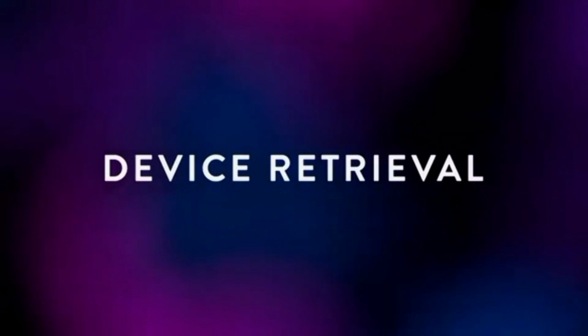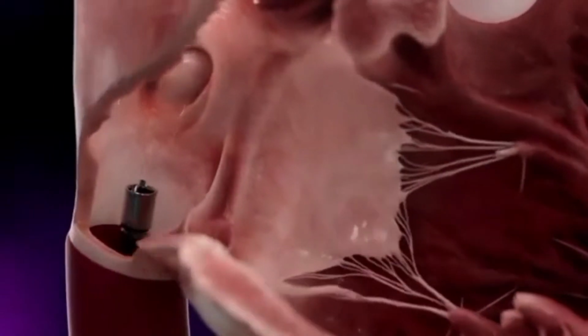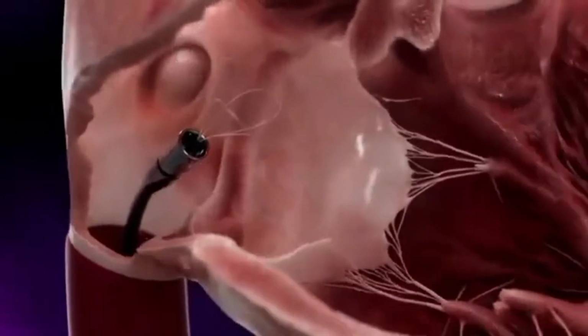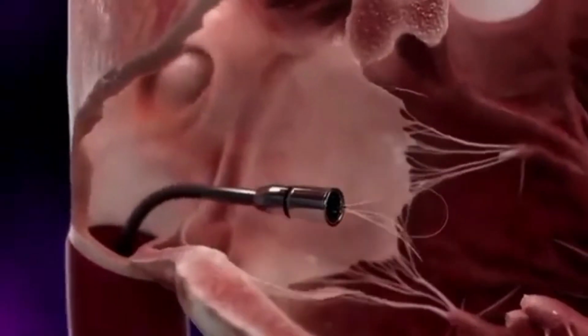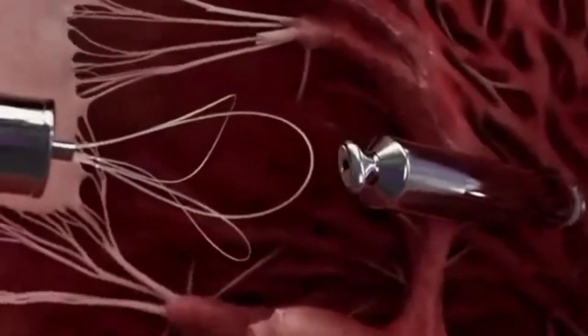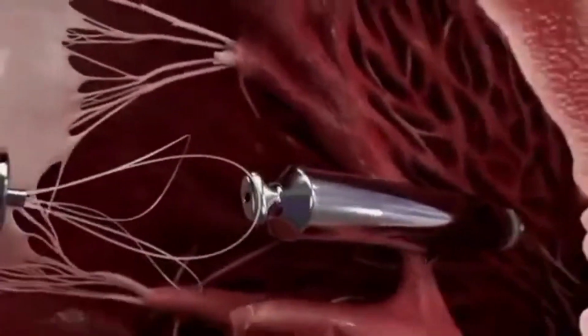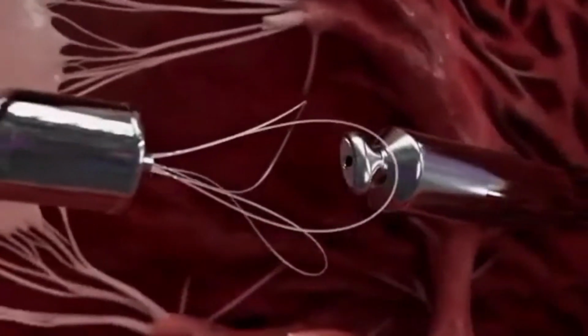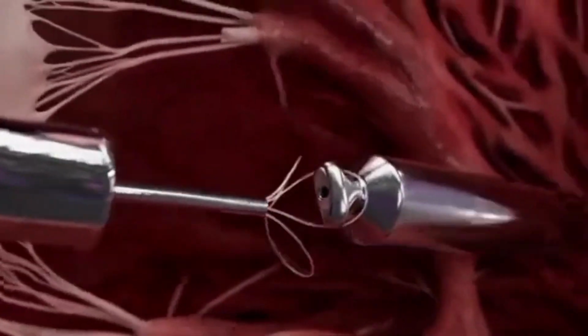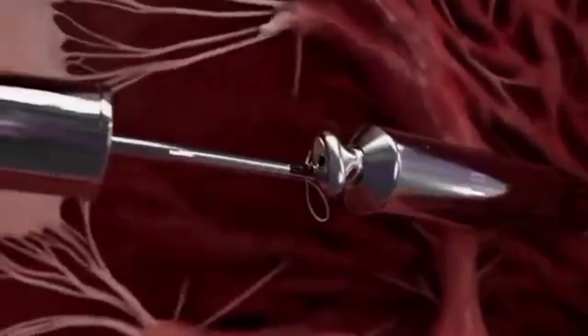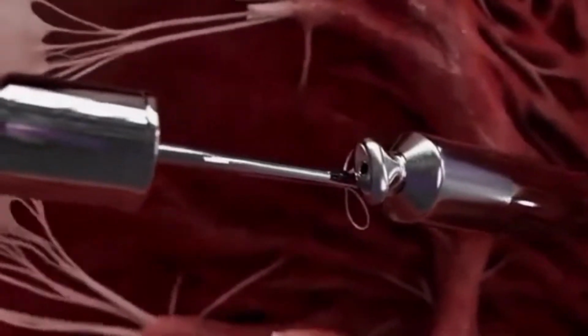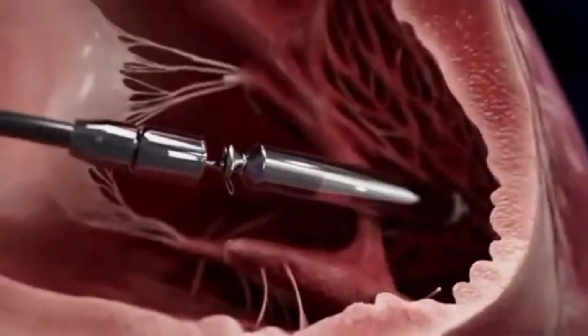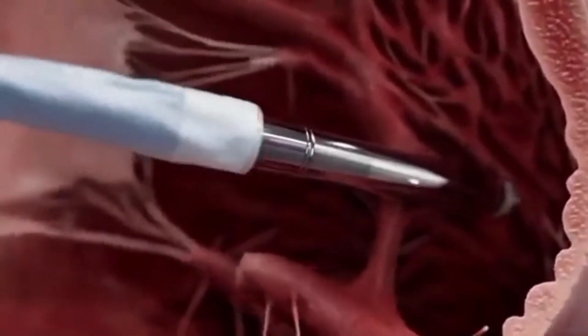The dedicated retrieval catheter can be used to retrieve an implanted leadless pacemaker acutely or long-term. During a retrieval procedure, the retrieval catheter is advanced into the right ventricle, aiming for the LP docking button. Once positioned, the snare is closed around the docking button and locked into place using the snare control knob. The leadless pacemaker is then docked to the retrieval catheter and covered by the protective sleeve.